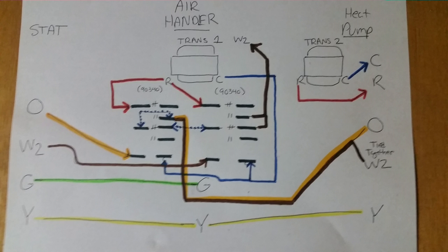Now when that relay is switched, the one on the left for the energized reversing valve, you see that the red goes from the normally closed to normally open. And that power flows to the O and W2 tied together outside at the unit. Therefore, that unit will have the reversing valve energized when the O and common energize the coil for the first relay. As you can see with the blue polka dots, there's jumpers on the relay.